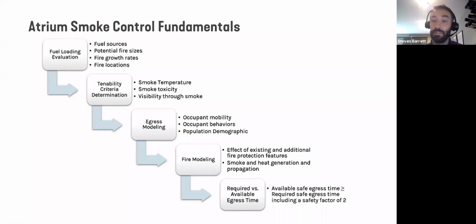Simultaneously, that fire model we talked about with the CFD is running, and then we compare those two models. We compare the available safe egress time, so how long conditions are tenable and safe, to the required egress time, how long it takes people to actually get out based on how many people are in there, their mobility factors and things like that, and then apply a safety factor.